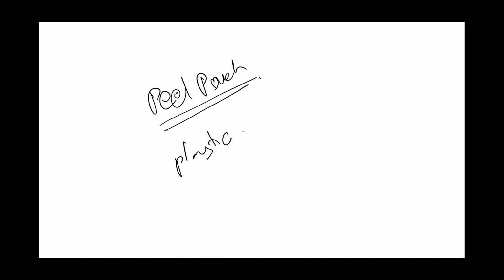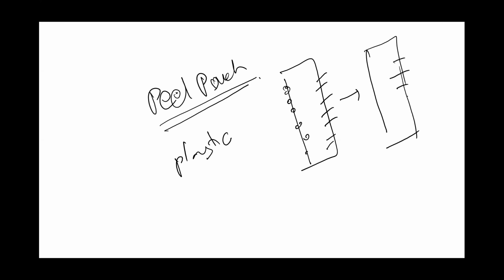These peel pouches, when loaded side by side in a sterilizer, is it all right to have the plastic side of one pouch face only the plastic side, and the paper face only the paper side? Ma'am, it depends upon how fast the conduction happens. The guideline says that the plastic side of one pouch should face the paper side of the other pouch, not plastic to plastic.